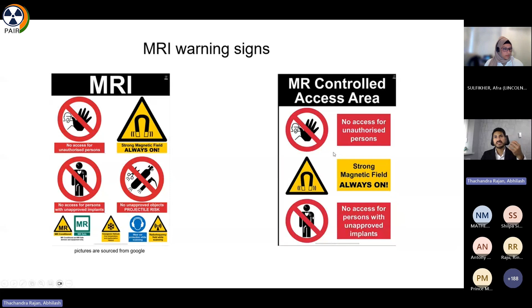Outside Zone 4, or outside the MR examination room, you can see the first warning sign, which includes: magnet is always on, pacemakers and implants are not allowed without checking, and no access for the unauthorized public. We also mention hearing protection in this. And outside the MR control access area, we can see this signboard.